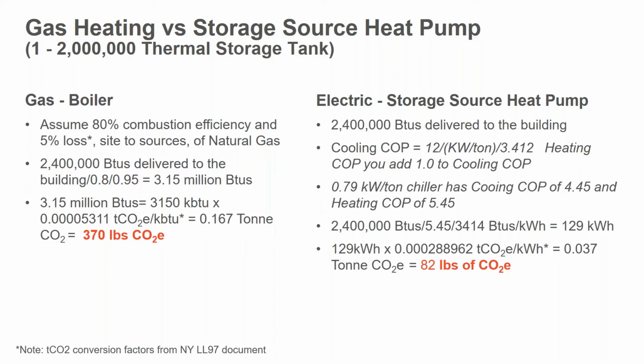Do the calculation. And on the carbon side of things, using the numbers from Local Law 97, you're looking at about 370 pounds of carbon equivalent there. Well, now let's do it with the electric storage heat pump. Well, we're trying. The goal is to deliver 2.4 million BTUs to the building. And I spoke about a COP. Everybody on the call here knows what a COP is, but we normally speak more in terms of kW per ton.